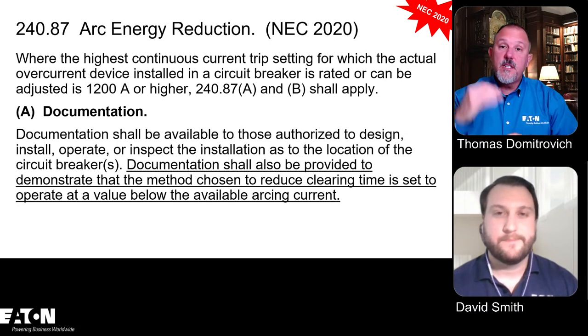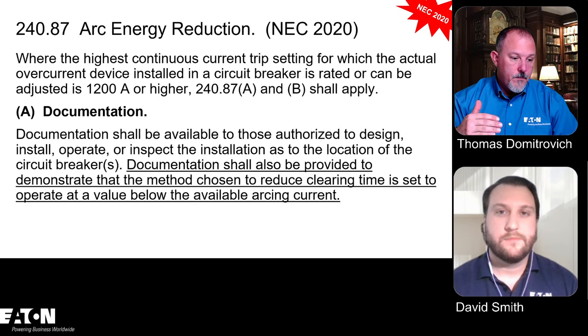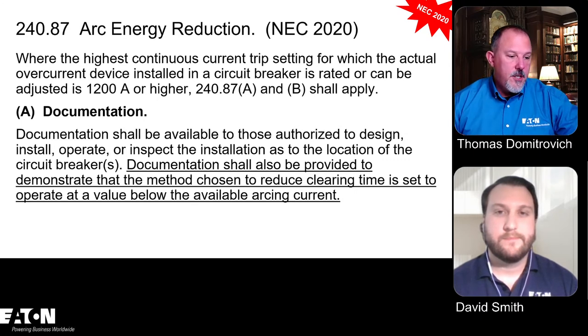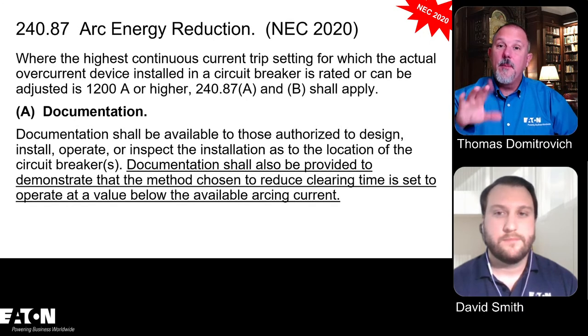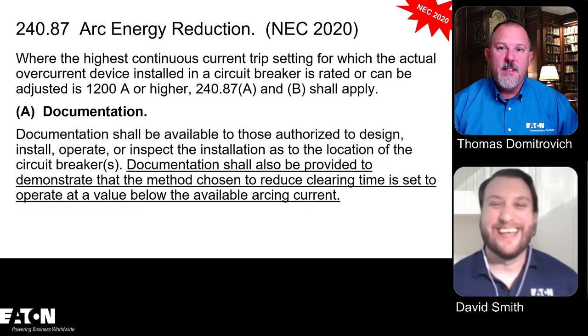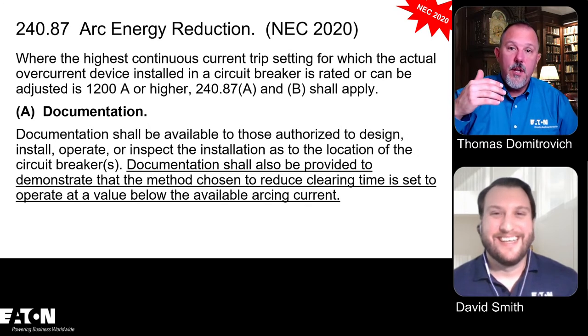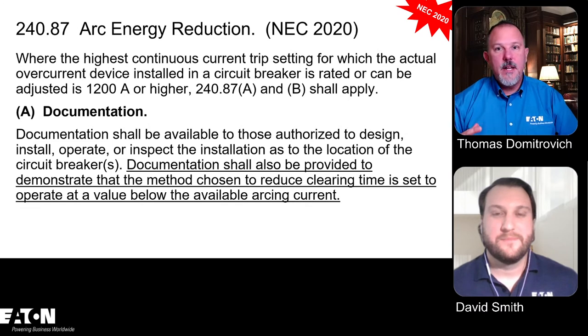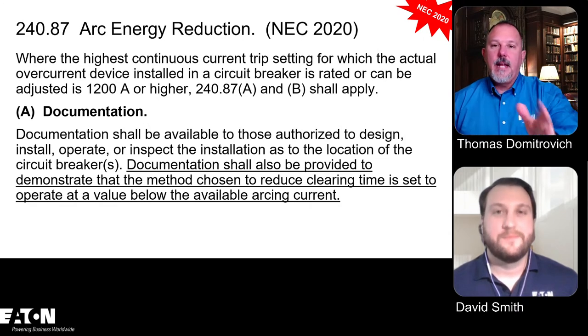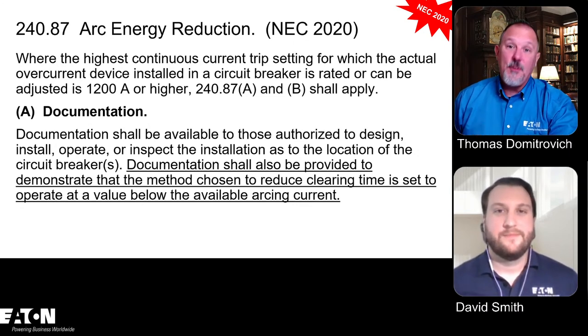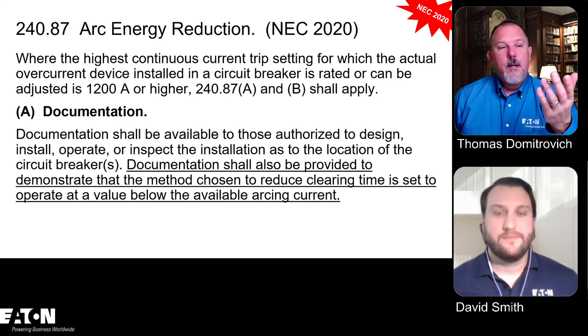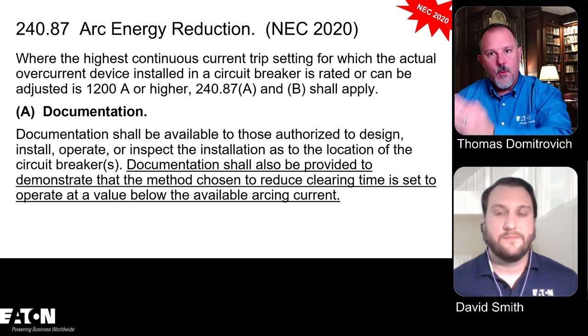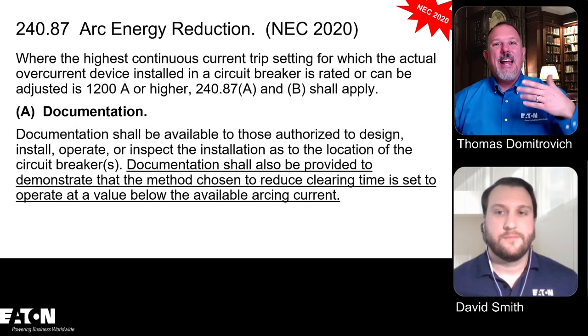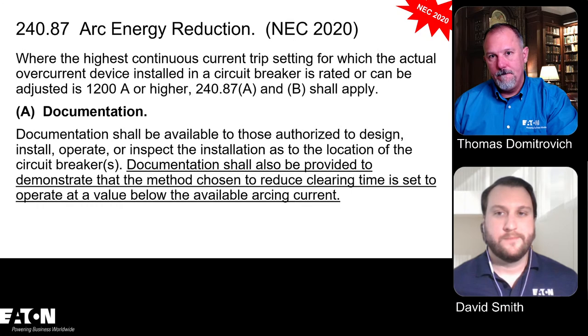Right. And there was discussion at the code panel where they wanted to say, look, the incident energy number can't be greater than this number. Yeah. They wanted to put, like, it can't be greater than 8 calories or 4 calories. But the issue that you run into, which some people say there's an issue, which I don't know, I lean more towards I like to have that number. Because if you just say, look, you can't have an incident energy number greater than this value, I don't care how you get there, you just have to get there, right? But what they'll tell you is that 70E is what drives the incident energy. And if the National Electrical Code said anything like that, then it would be stepping on the toes of 70E, if that makes sense. So it does.